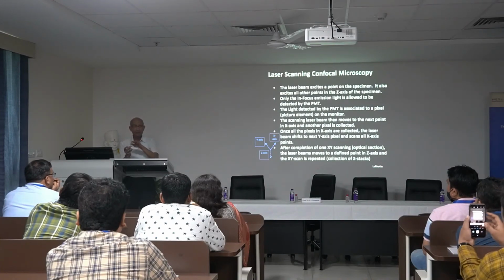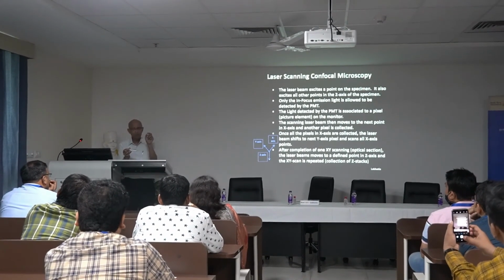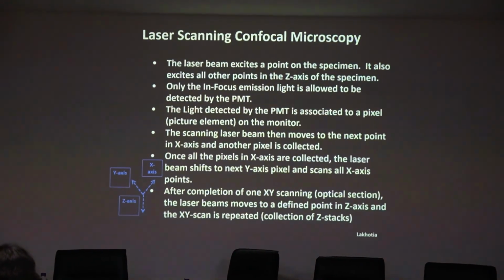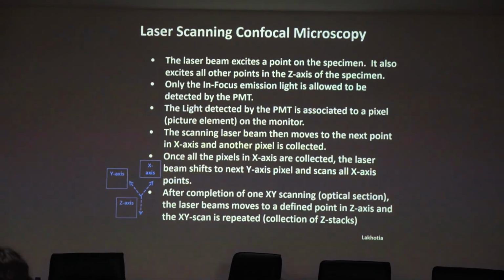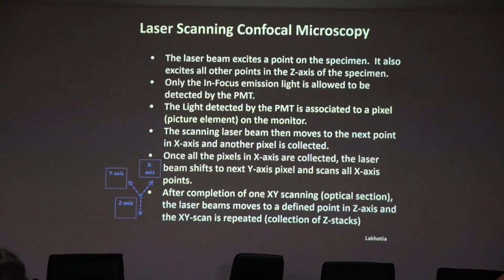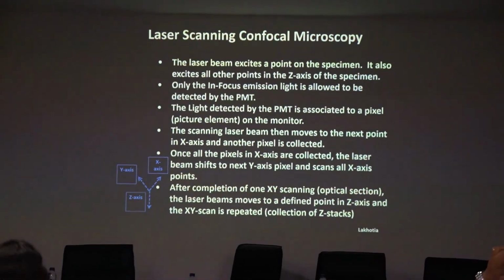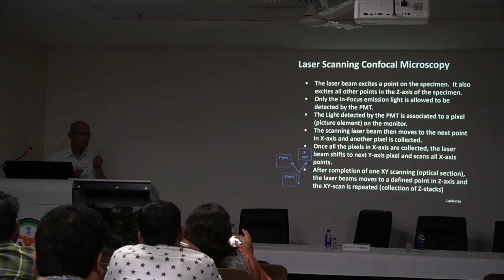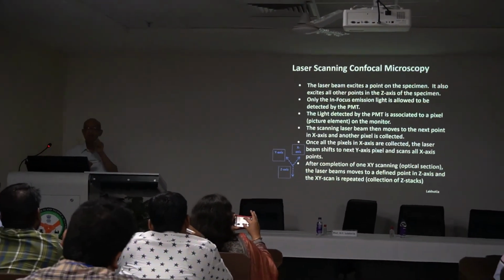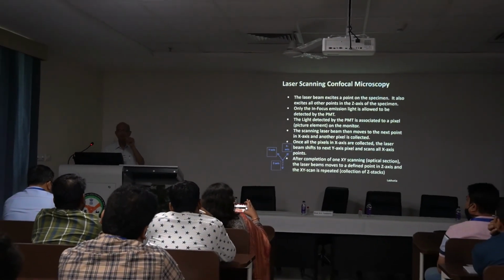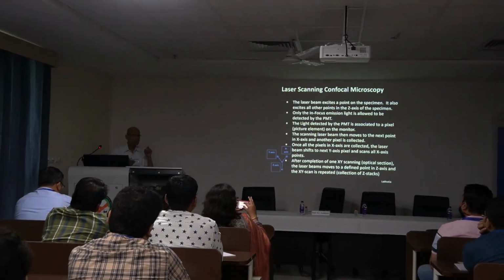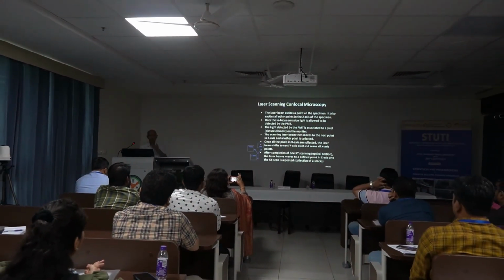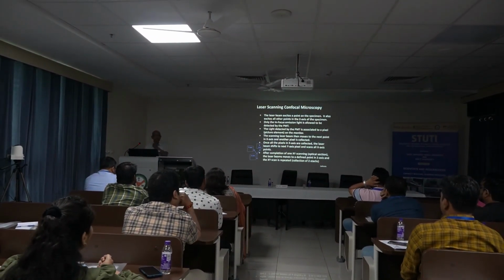each point, and these distances, how much it will move in the x-y direction, that's where the whole confocal scanning head becomes a marriage of mechanical and digital things together. You must have very precise motors, precise mirrors that can oscillate and move by less than a micrometer. You can choose 0.2 micrometer distance, you can choose 0.5 micrometer distance that each axis will do.